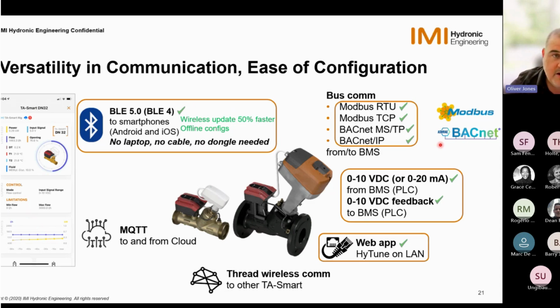So there are 4 that we can select from effectively, depending on how you wire it and how it's being controlled. And again, our 0 to 10 VDC or 0 to 20 milliamp or 4 to 20 milliamp is our input from our BMS PLC, so we can control the valve that way. And we can also get feedback back to the BMS, which is just 0 to 10 volts VDC. We don't do 0 to 20 or 4 to 20 milliamp on output.